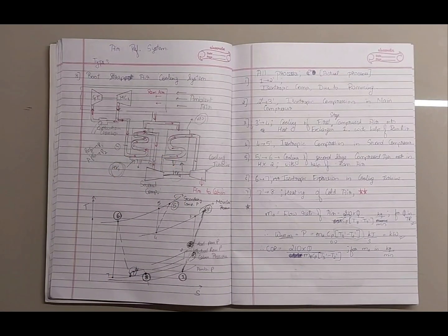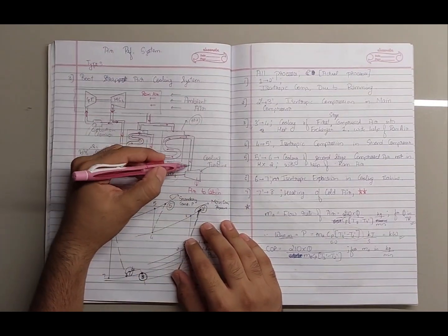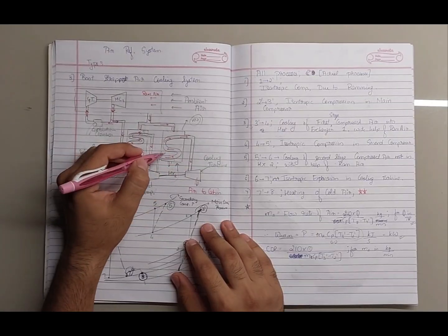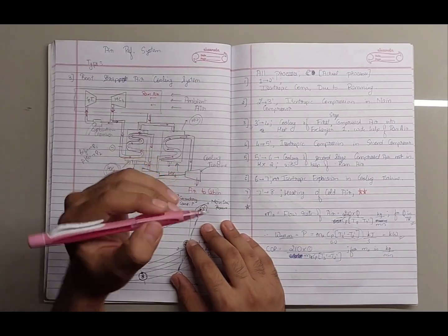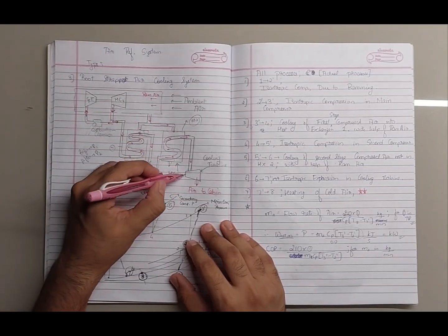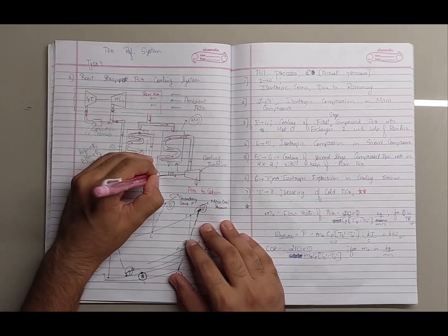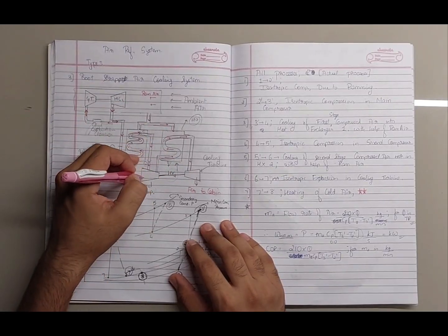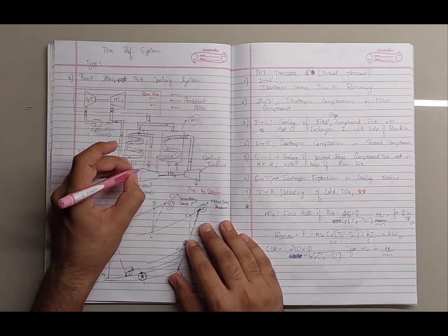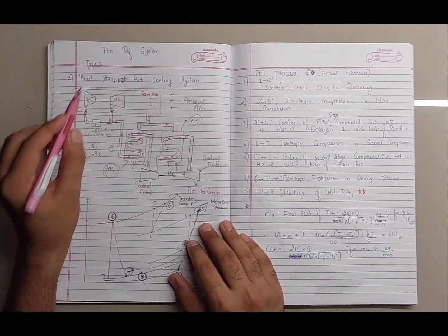And we know that a turbine doesn't require work, it produces work, because an expansion process generally produces work, the work being negligible. We don't consider that, but a turbine always produces work. So as the air passes through it, it has its natural kinetic energy as it is pressurized, so it rotates the turbine, it exits by expanding. As it rotates the turbine, it rotates the shaft, and this shaft provides power to the secondary compressor. So the power provided to the secondary compressor is totally bootstrapped.